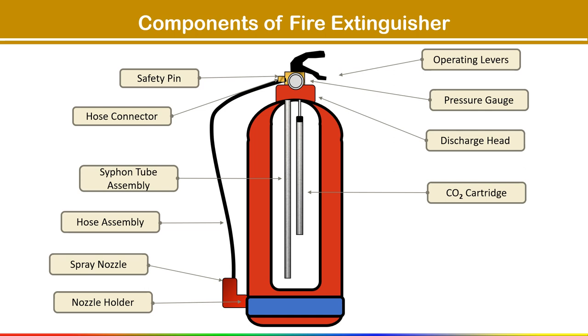When the fire extinguisher is activated by pressing the handle or lever, it punctures or opens the CO2 cartridge, releasing the compressed carbon dioxide into the cylinder. The expelled CO2 builds pressure inside the cylinder, forcing the extinguishing agent out through the discharge head or nozzle to suppress or extinguish the fire. The final component is the plastic boot, which serves as a protective cover for the bottom of the extinguisher, preventing damage to the cylinder and keeping the base clean.